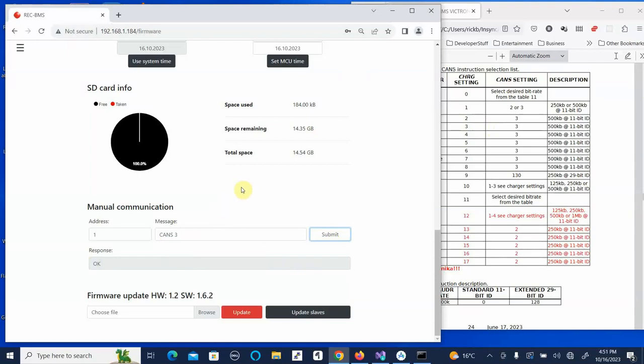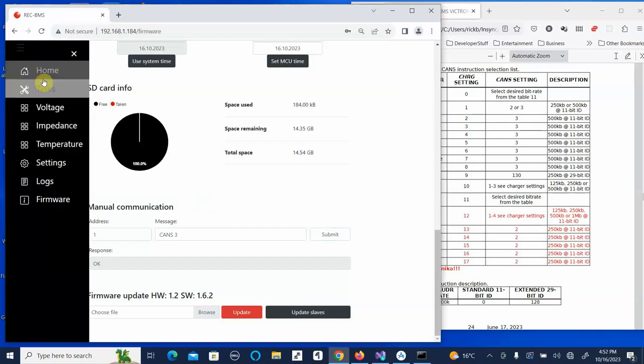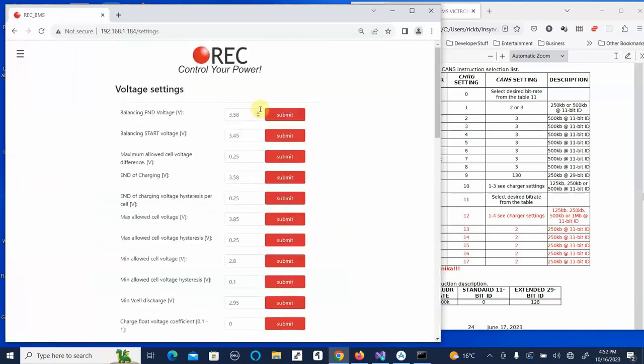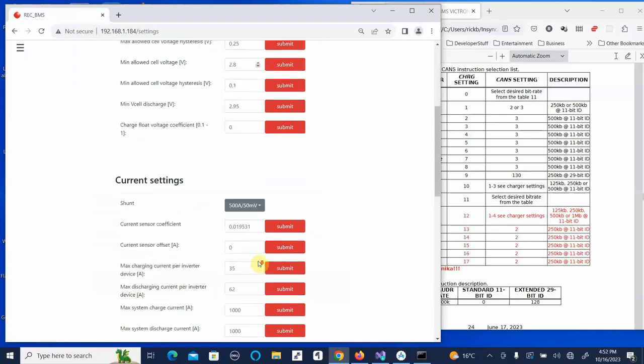A couple other parameters you will want to set up. So let's go back to settings. Your voltage settings are pretty well roughed in for most LiFePO4 or LFP type of batteries. You can tweak them a bit as needed here, but the areas we do need to focus on are, one, our current settings. So what shunt are we using? Did you get a 200, a 300, a 500, or 1,000, or is it some custom value? If it's a custom value, then you'll go in and set the coefficient. If it's a standard value, it will set the coefficient for you. Sensor offset is usually left at 0.